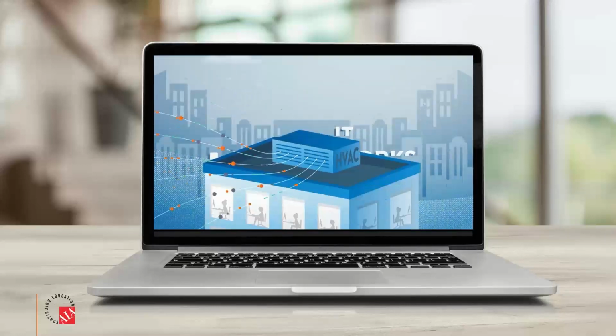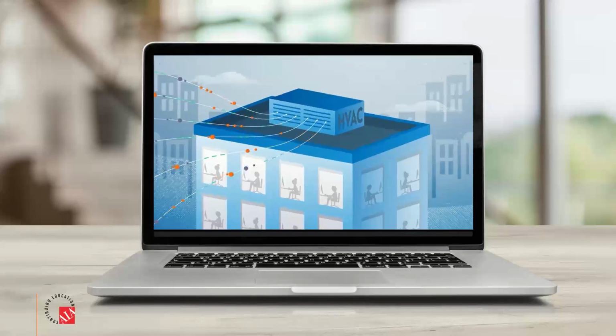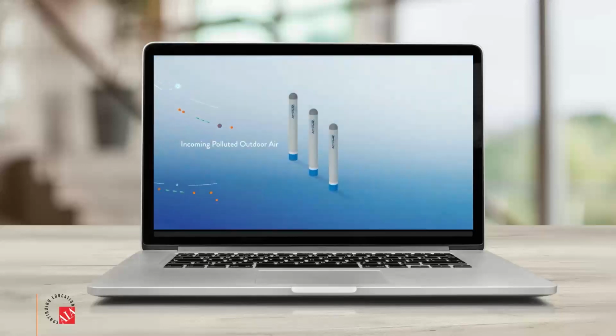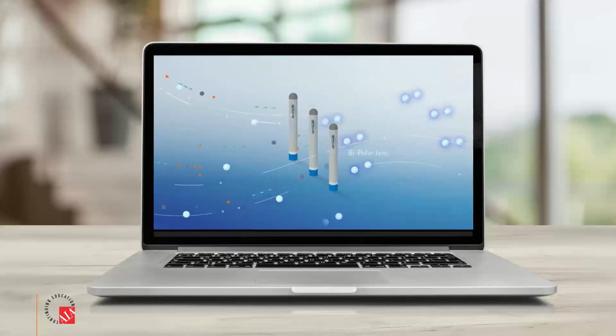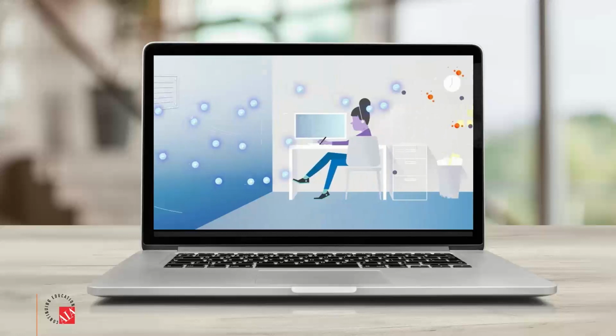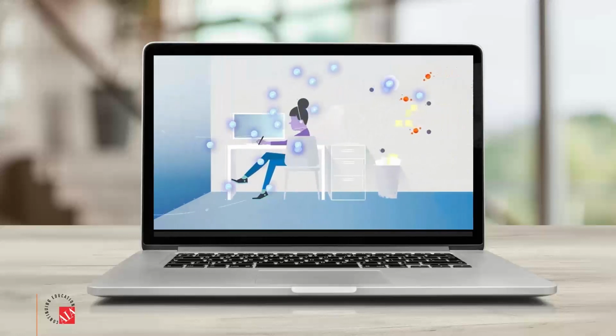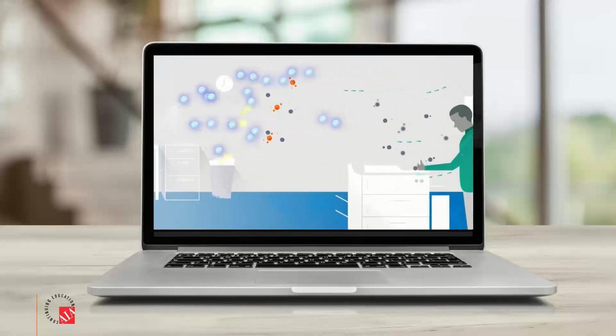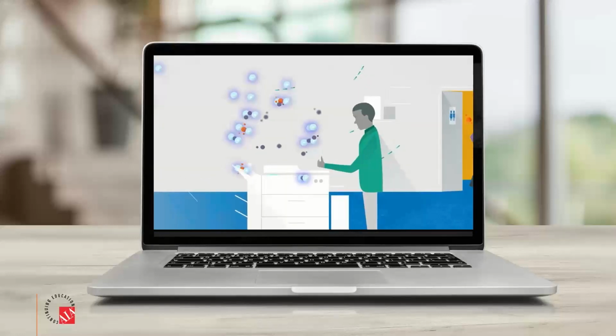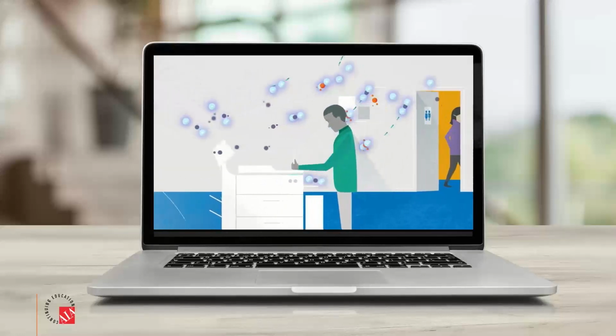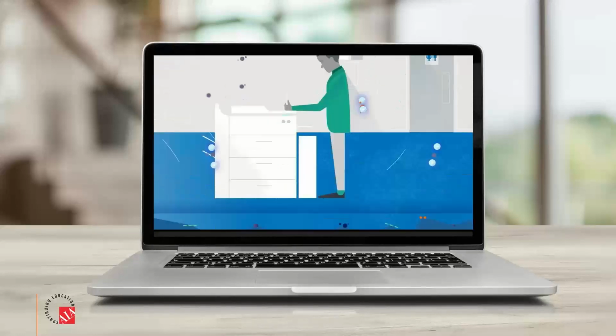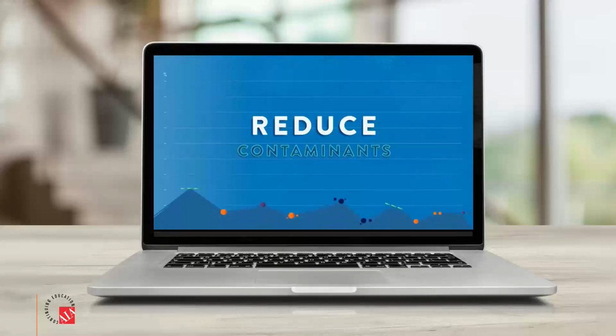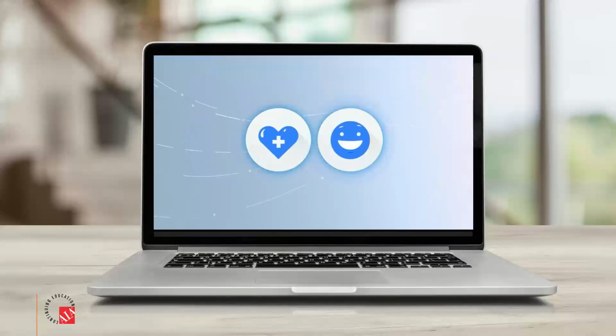When outdoor air comes into a building, oxygen molecules are carried over specially designed bipolar ion tubes. An energy field converts these molecules into positively and negatively charged ions. These ions then travel into occupied spaces to seek out oppositely charged bad air particles, VOCs, and odors. When they combine, it forces them to break down and drop out of our breathing range to reduce contaminant levels and improve our health and wellness.